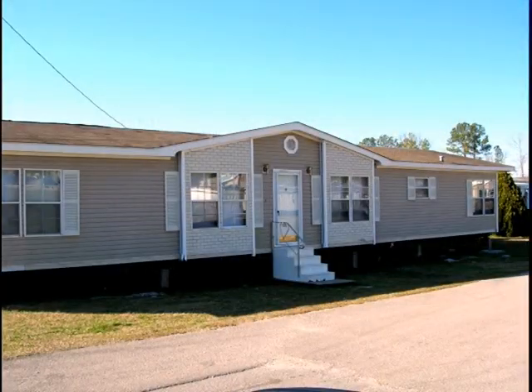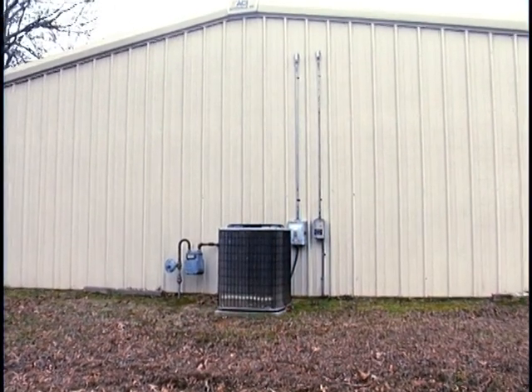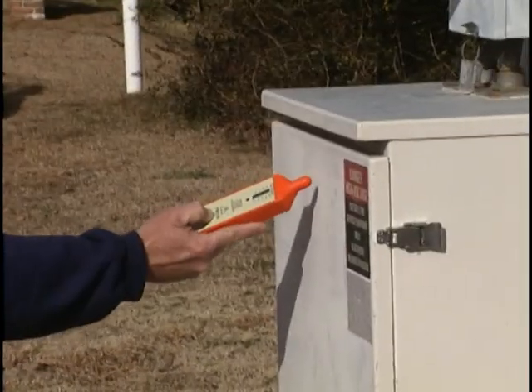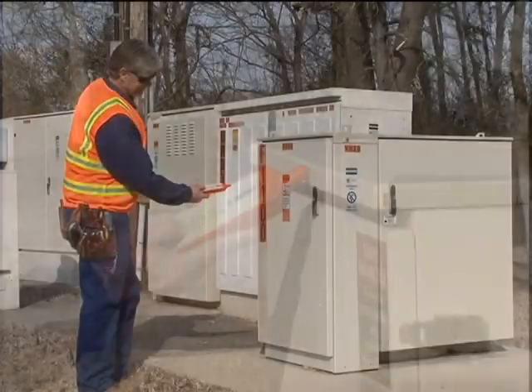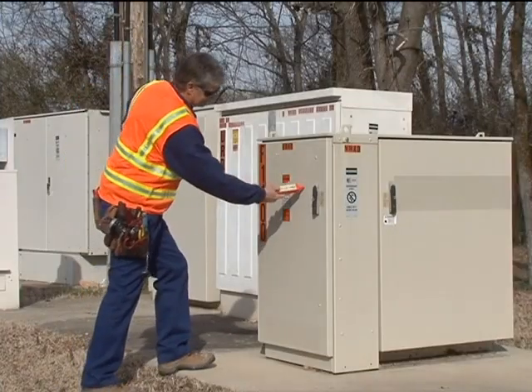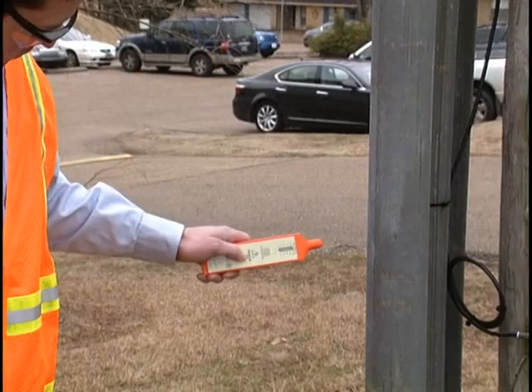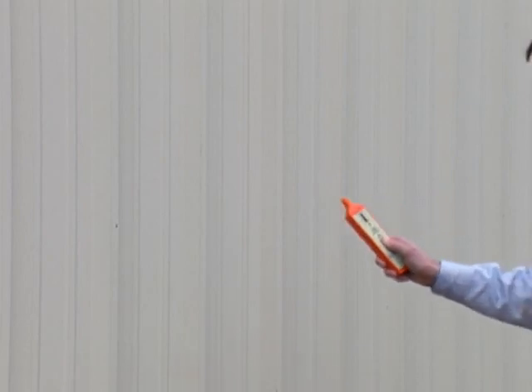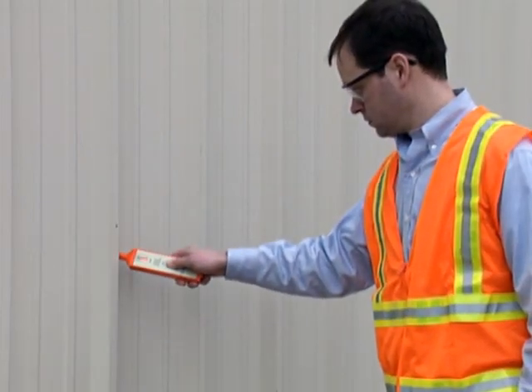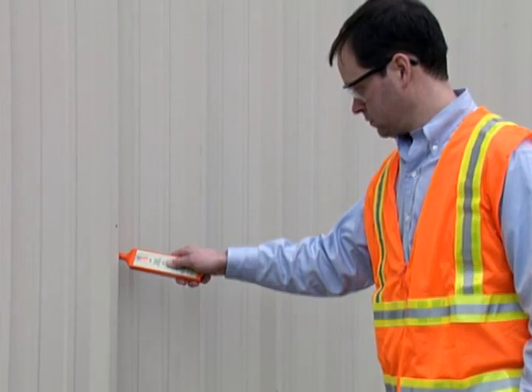Note that any facility such as this mobile home, a metal building, metal conduit, virtually any conductive surface that should be grounded should not read any AC voltage. If any AC voltage is detected, the grounding of the facility should be suspect. This metal building has been purposely energized, as could happen in the case of a power fault within the structure.